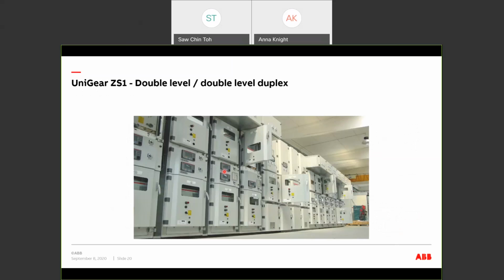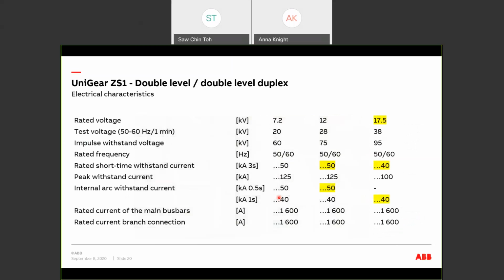Next, we have a double level cubicle. For this type of cubicle, we can stack 2 circuit breakers or 2 contactors in 1 cubicle. This is the design that we normally use for the marine segment where space is an issue. The maximum voltage rating is 17.5 kV. The short time withstand is 50 kA 3 seconds for 12 kV, 40 kA 3 seconds for 17.5 kV. For internal arc, we can meet a maximum of 50 kA 0.5 second for 12 kV and 40 kA 1 second for 17.5 kV. The maximum current that we can support for the double level UniGear ZS1 cubicle is 1600 amps.